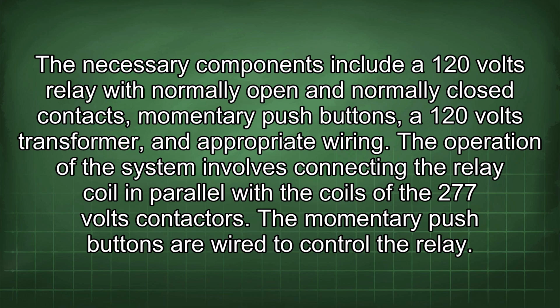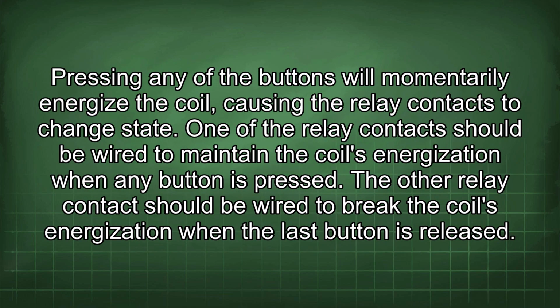The operation of the system involves connecting the relay coil in parallel with the coils of the 277 volts contactors. The momentary push buttons are wired to control the relay. Pressing any of the buttons will momentarily energize the coil, causing the relay contacts to change state. One of the relay contacts should be wired to maintain the coil's energization when any button is pressed. The other relay contact should be wired to break the coil's energization when the last button is released.